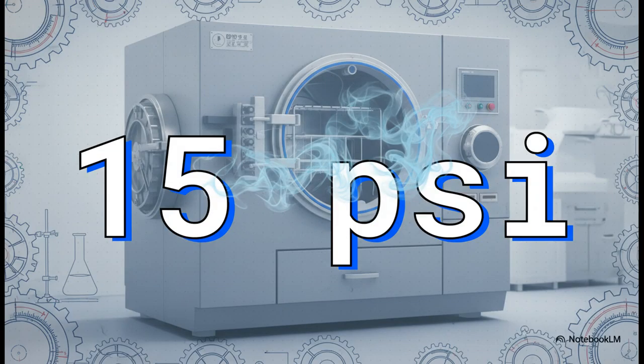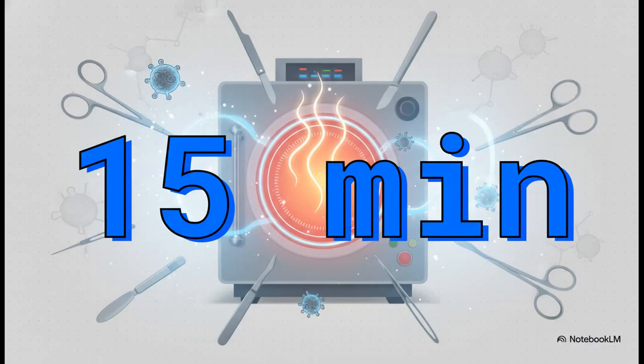At 15 pounds per square inch of pressure, the boiling point of water gets pushed all the way up to exactly 121 degrees Celsius. And that right there, that perfect marriage of temperature and pressure, is the first part of the magic recipe for sterilization. And here's the final piece of the puzzle. You hold it at that temperature and pressure for at least 15 minutes. Temperature, pressure, time. That's the combo, the 1-2-3 punch, that guarantees everything is 100% sterile.